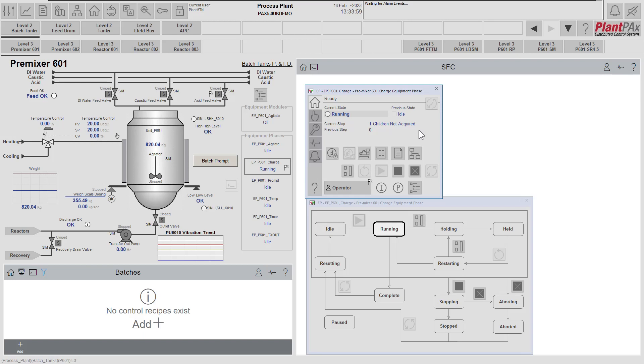The OOA framework simplifies the task of ownership — making sure that I own the devices I want to use — and also simplifies understanding if any of the devices I'm using has an issue and I need to do something about it, or go to hold so that the operator can resolve the issue. In order to own my devices, we have to tell the equipment phase to acquire them. In this case the implementer has chosen to leave that to the user, so we have to select this button here to acquire and tell the equipment phase to try and acquire its children.